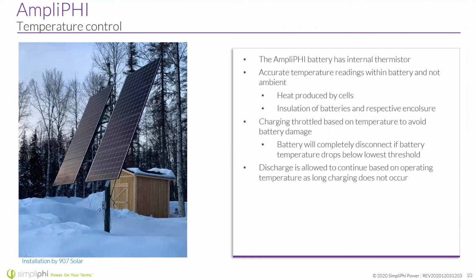Let's also look at temperature control as a key feature. The AmpliPhi battery has an internal thermistor for accurate temperature readings within the battery, not ambient. The temperature readings are coming from the cells - that's the location of the reading. This allows you to factor in things like heat produced by the cells. The cells are really the main thing to think about regarding battery temperature - that's where damage could occur from low or high temperature charging. So that's where it's key to be measuring, so we don't get incorrect measurements because we're measuring directly at the cell. We get to incorporate the heat produced by the cells, the insulation of the batteries, and the respective enclosure they're in.